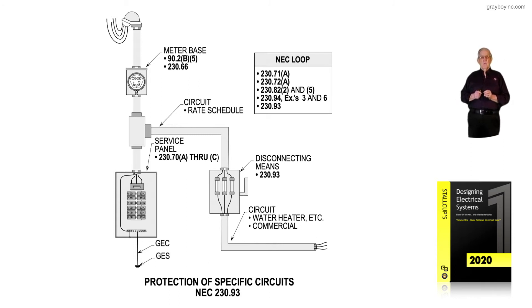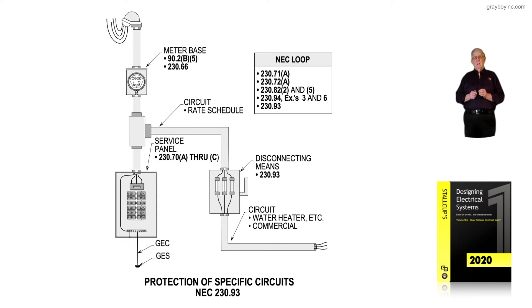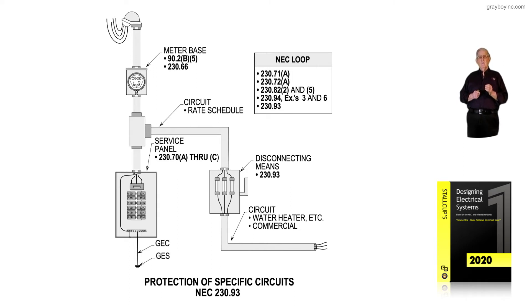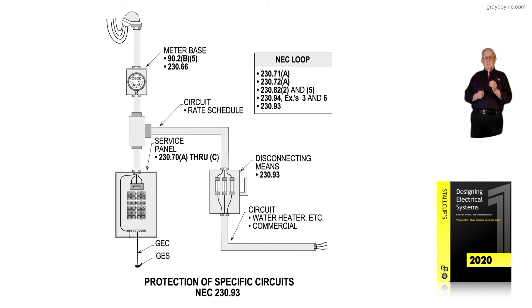The service equipment has to comply with 230.70A through C, but the tap ahead of the main has to comply with 230.82. Notice we're tapping ahead of that main, supplying over to that disconnecting means, and once we get to the tapped area where those conductors are feeding the switch, we have to have overload protection of those conductors. We're feeding a water heater in a commercial building, and the tap is complying with 230.82, items 2 and 5.